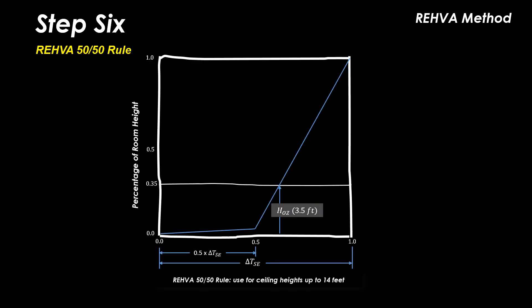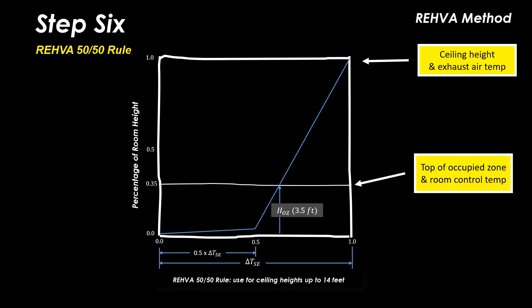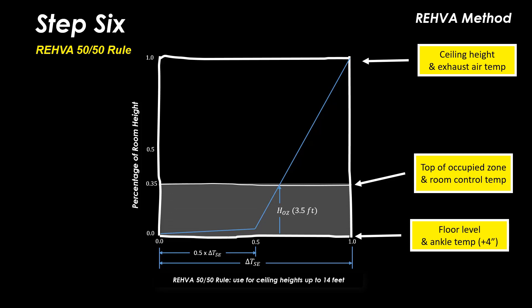The REHVA 50-50 rule can be explained by examining the temperature gradient in the space relative to the total space height. At the top is the ceiling height at which the exhaust or return inlet is located. With a 3.5 foot high occupied zone, the top of the occupied zone is 35% of the total height. At the base is the floor level where the supply air outlet is located. The occupied zone is shaded grey in this graphic.